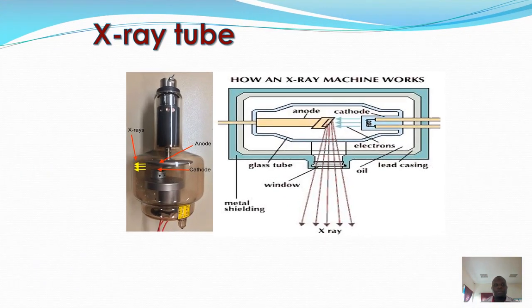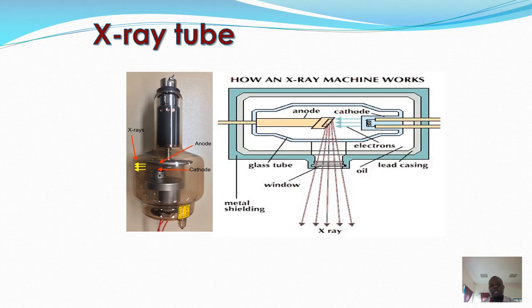We have two diagrams of the X-ray tube: the actual tube and the physics diagram used for study purposes. As seen on the diagram, the X-ray tube has metal shielding as its outer surface, a glass tube which is evacuated to form a vacuum, and it has an anode and a cathode.